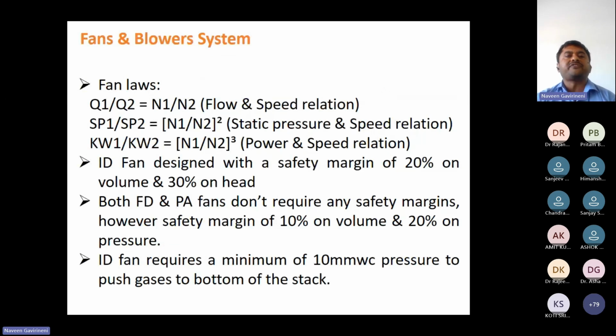So these are the fan affinity laws, as you know: Q1 by Q2, flow, is proportional to speed. For static pressure, if you increase the fan speed, pressure goes as the square of the speed. And this is the power and speed relation: if you increase the fan speed 3 times, the power will be obtained from here. So there is a margin on the fans.